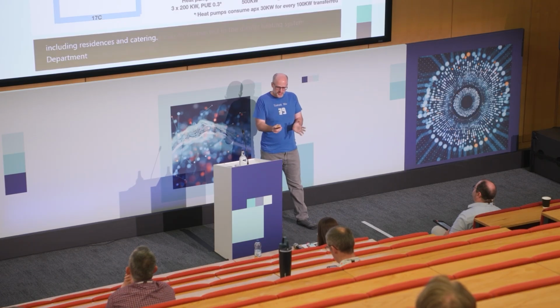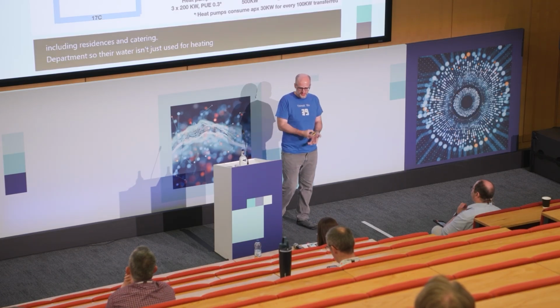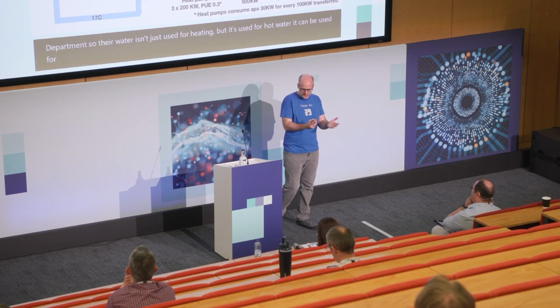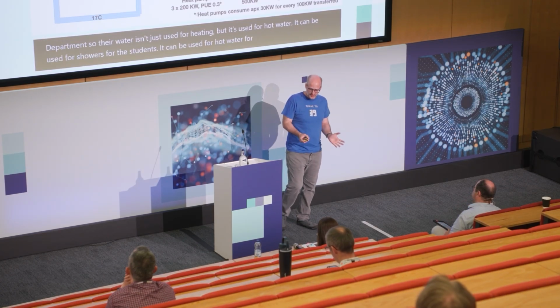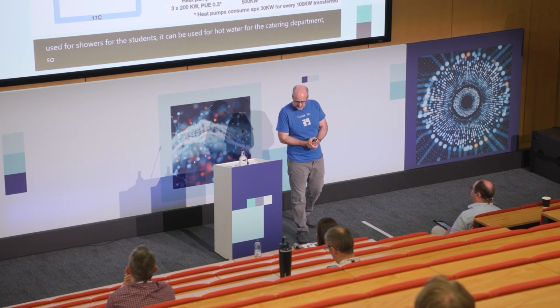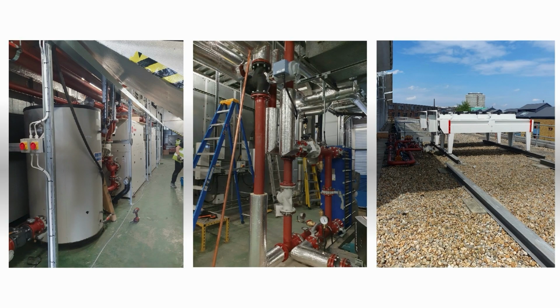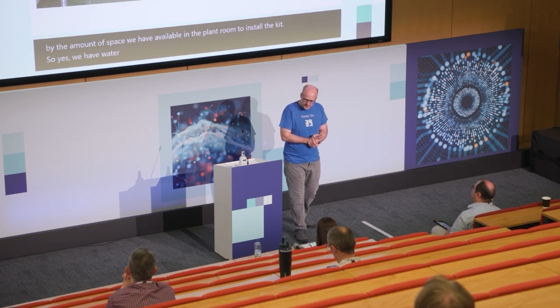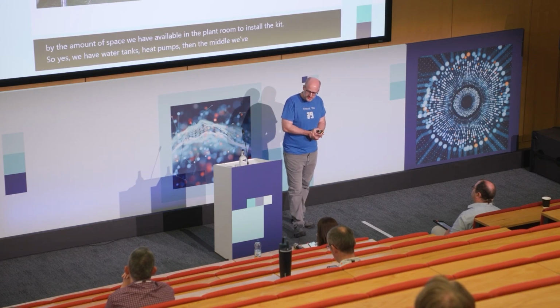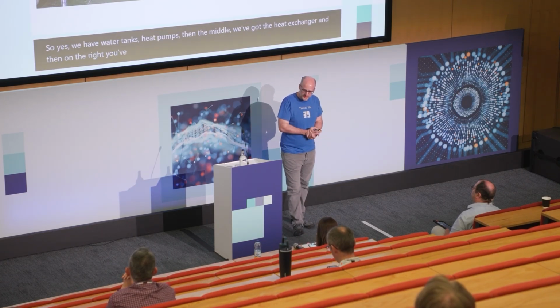So the water isn't just used for heating, but it's used for hot water. It can be used for showers for the students. It can be used for hot water for the catering department. So it is actually being used all year round. And then this is what it looks like upstairs in the plant room. You can see that the space is quite tight, and actually the 390 kilowatts I mentioned is somewhat driven by the amount of space we have available in the plant room to install the kit. So we have water tanks, heat pumps. Then in the middle, we've got the heat exchanger, and then on the right, you've got the dry air coolers outside.